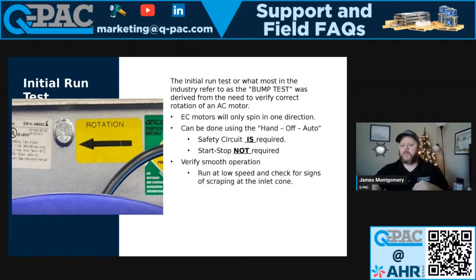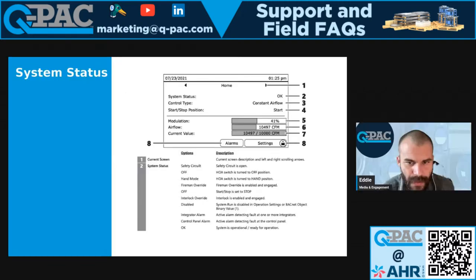You may not get CFM if all of the ductwork is open, or if your doors are open, you may need to close those, because the way we actually pull that is with the pressure transducer. But you do need to verify that that's moving. Later on, that can be calibrated with the controls and the test and balance team, but you should see some CFM. If you don't, then we're going to need to look into it and say, are we getting a signal from this thing? So here's that system.